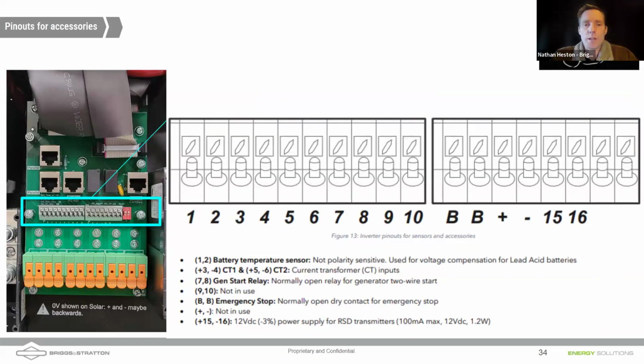So Daniel's showing the full control bar here, what those different pins are. Pins 3, 4, 5, and 6 you'll always use. Those are the CTs that come with the inverter. And then BB, pins 11 and 12, you would use those always as well. Almost every jurisdiction is going to require a rapid shutdown button on the outside of the house to make sure you can shut down the inverter and the solar given an emergency situation with first responders. And then that generator start relay, that's the normally open dry contact, and that'll connect with pins 3 and 4 in our generators.